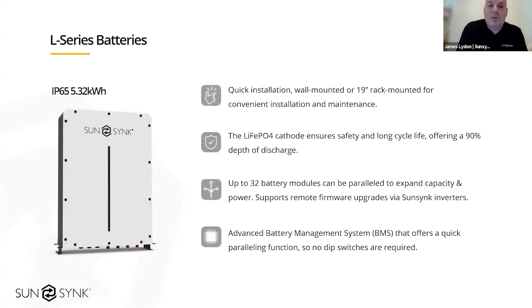All of our batteries are LiFePO4, so really safe battery chemistry. And they all have a 90% depth of discharge. We can have up to 32 batteries connected in parallel, so it gives you an idea of the scalability of the system. With our low voltage hybrid inverters, we can parallel up to 16 of them together, with a total of 32 batteries connected to that paralleled system, essentially.